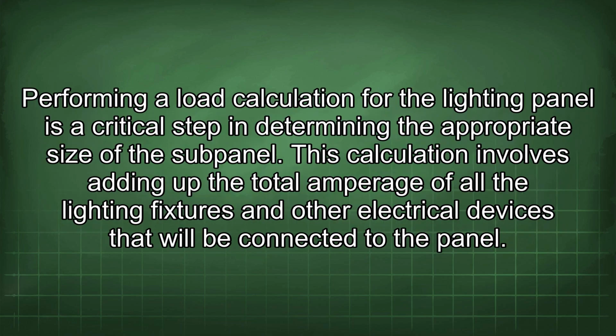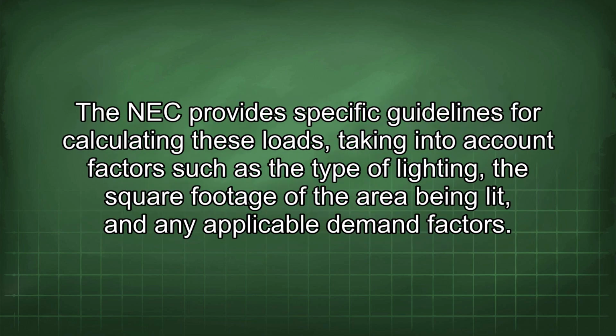location. Performing a load calculation for the lighting panel is a critical step in determining the appropriate size of the subpanel. This calculation involves adding up the total amperage of all the lighting fixtures and other electrical devices that will be connected to the panel. The NEC provides specific guidelines for calculating these loads, taking into account factors such as the type of lighting, the square footage of the area being lit, and any applicable demand factors.